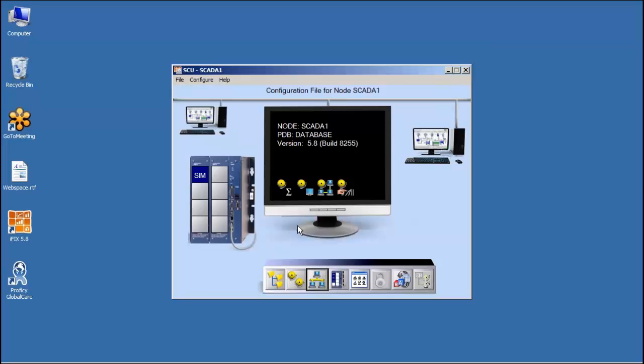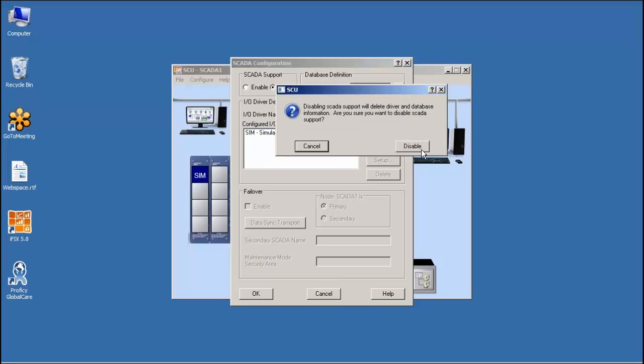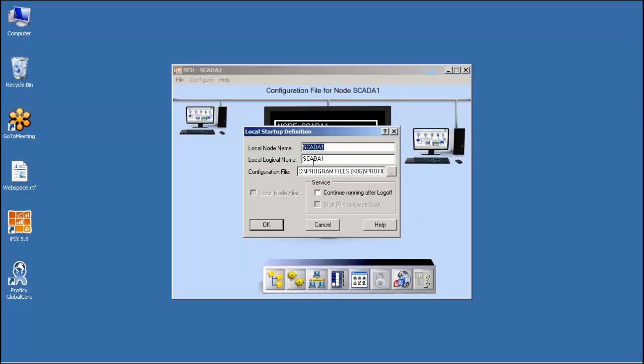If I was a view node, or I wanted to be a view node and turn off the SCADA portion of this, I could click on the SCADA configuration right here, and simply disable SCADA support. And that turns me into a view node. Notice the PLC disappears because I don't need drivers, and the database disappears from the list here. Of course, as a view node, I'd probably change my name to something like view1.